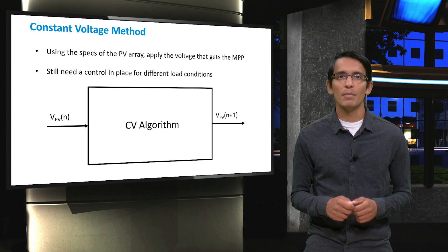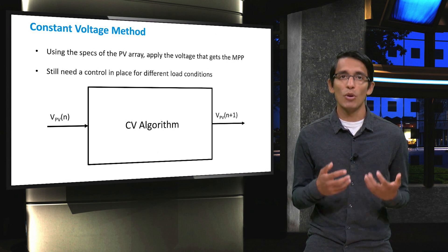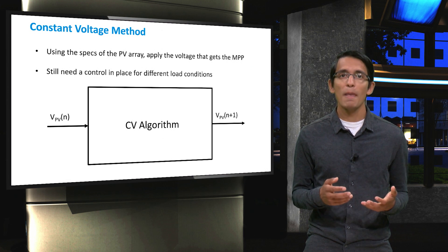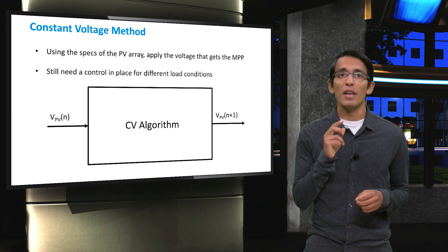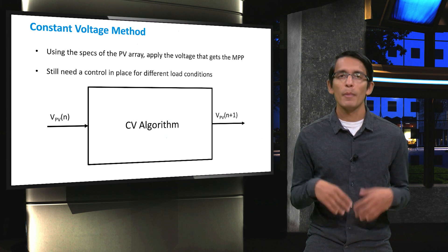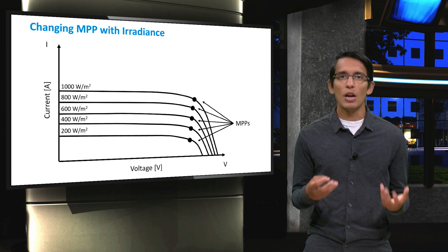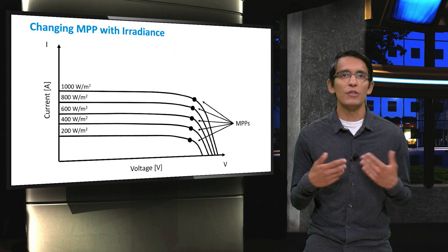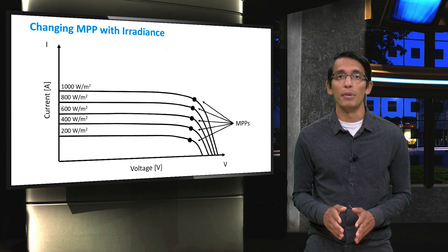One major drawback is that the system has to be hard-coded based on the panels. Since the MPPT logic is programmed in the power electronics components, this means that those components will only work if they are attached to specific panels with a specific VMPP. Furthermore, changes in irradiance and other conditions can cause the VMPP to shift and this will mean that running a constant VMPP technique will result in less than ideal power output.